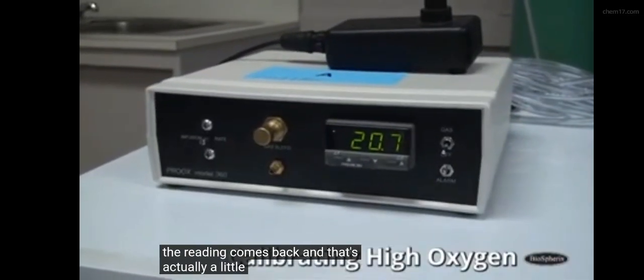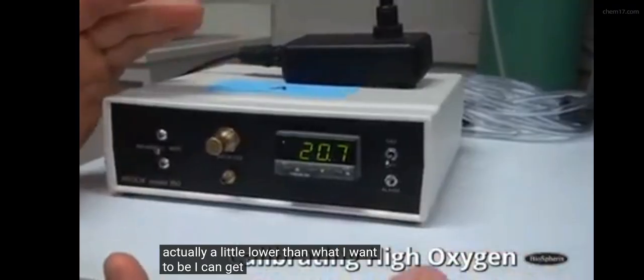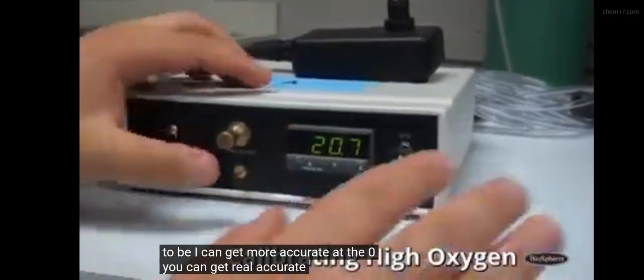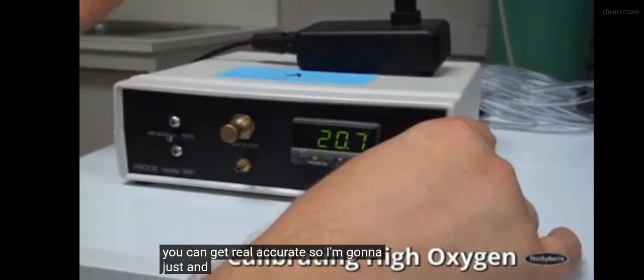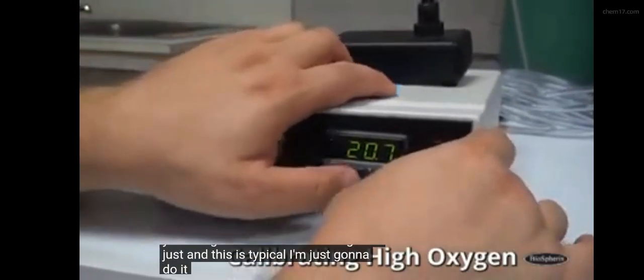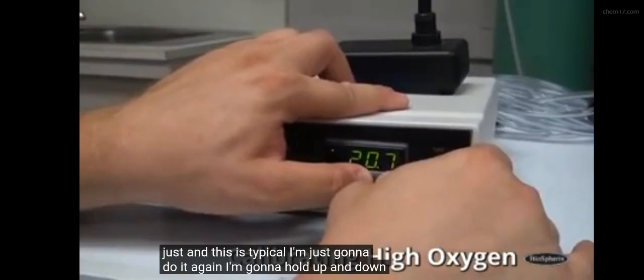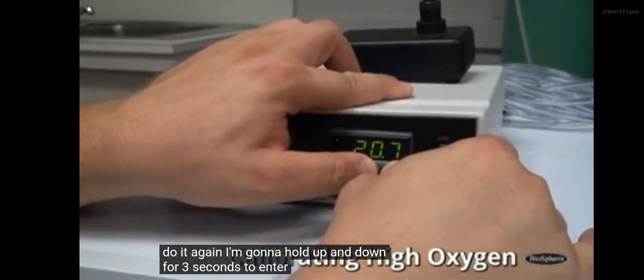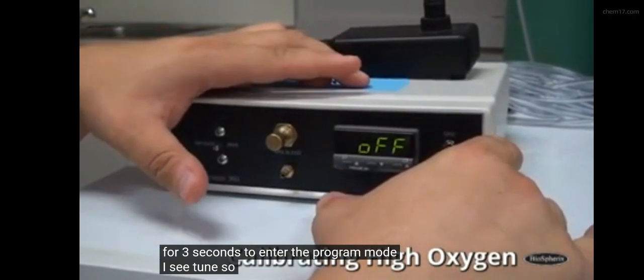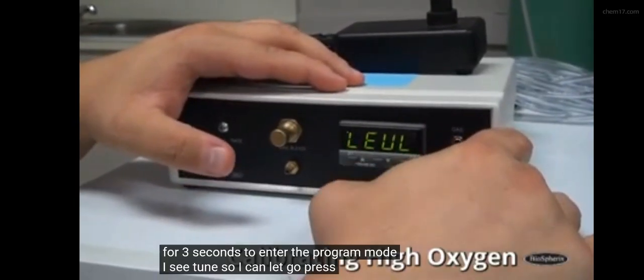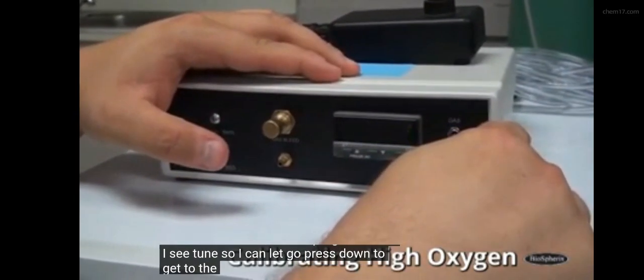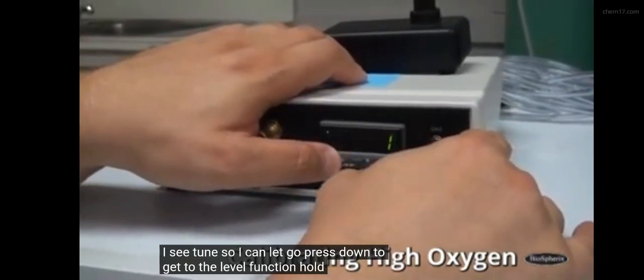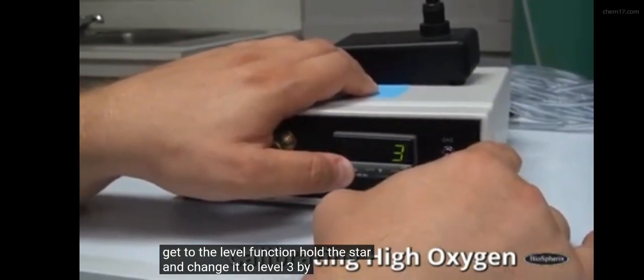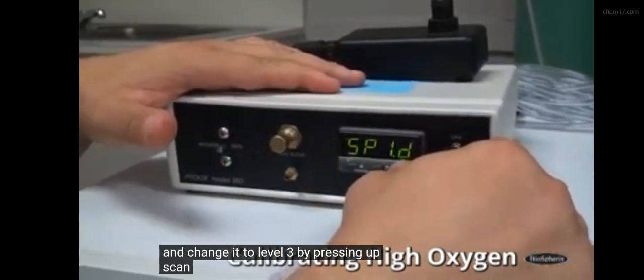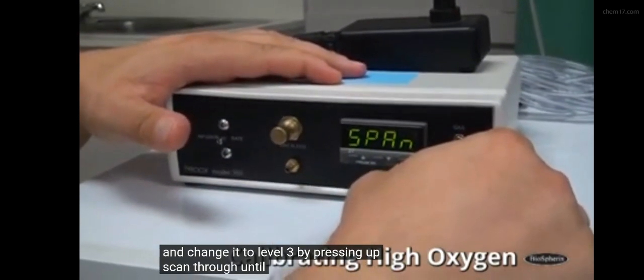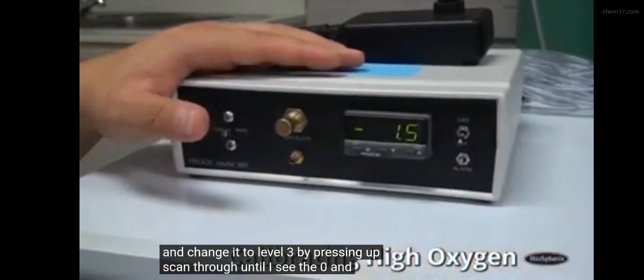And it's actually a little lower than what I want it to be. I can get more accurate. The 0 you can get real accurate. So I'm going to just do it again, and this is typical. I'm going to hold up and down for 3 seconds to enter the program mode. I see tune, so I can let go. Press down to get to the level function. Hold the star and change it to level 3 by pressing up. Scan through until I see the 0.